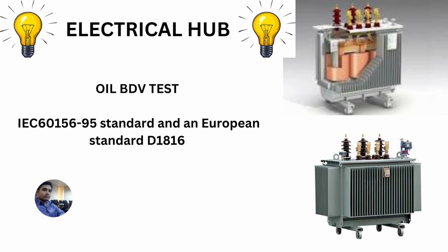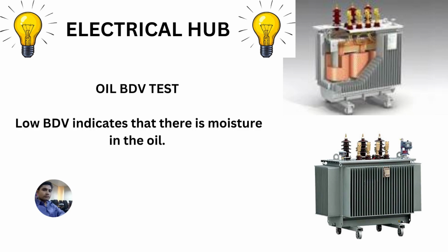There are two electrodes, and we maintain a gap of 2.5 mm between them according to the IEC standard. When we increase the supply, the oil's dielectric strength will break down at a certain voltage, and that voltage is the dielectric strength of the transformer oil. If there is a low BDV, meaning a low breakdown voltage, where the dielectric strength breaks down at a lower voltage, it means there is moisture in the oil.